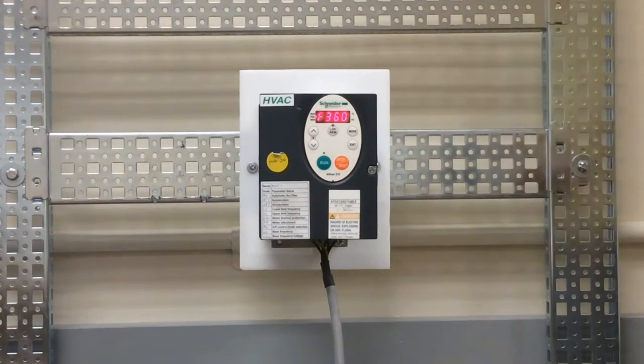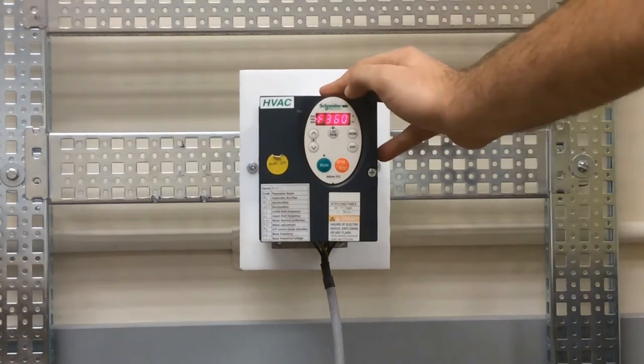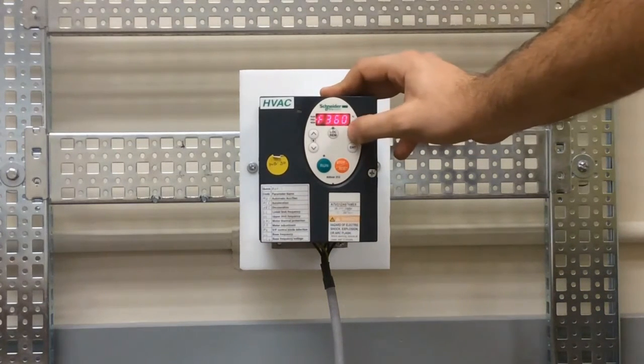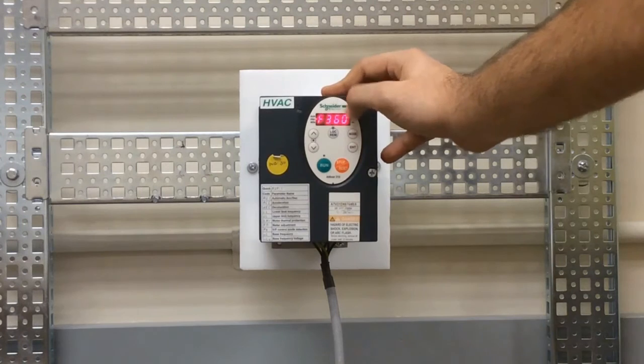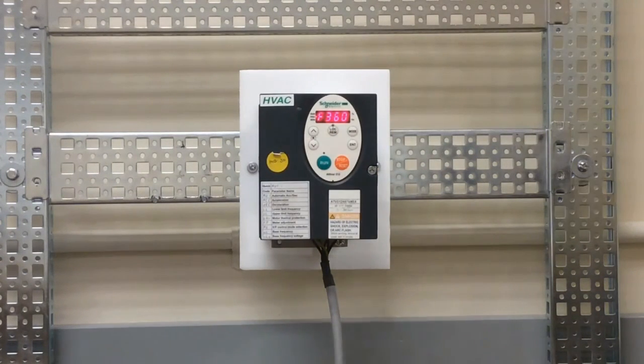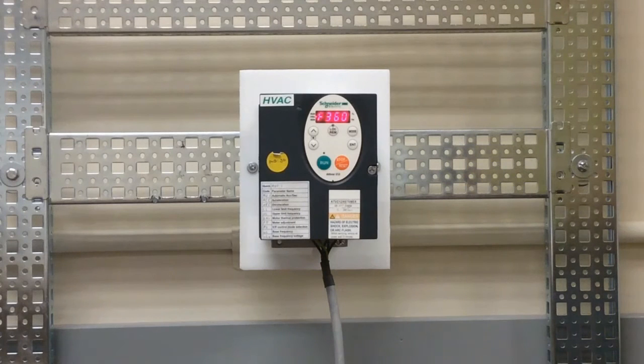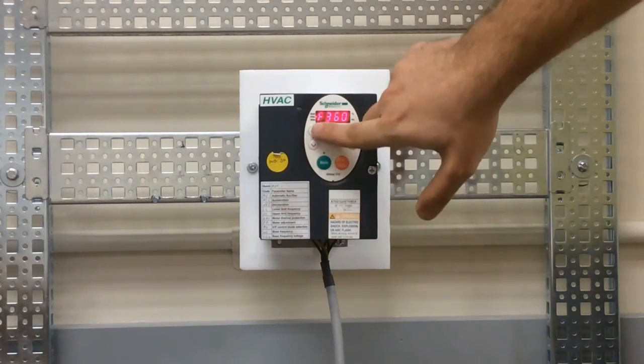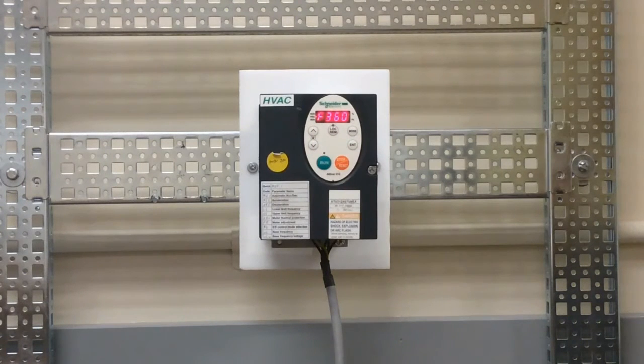Just press enter. The next parameter you'll have to go to is to make sure that we set the FMOD parameter under the AUF menu to three. This allows us to use the up and down arrow keys in front of the drive to set our set point.